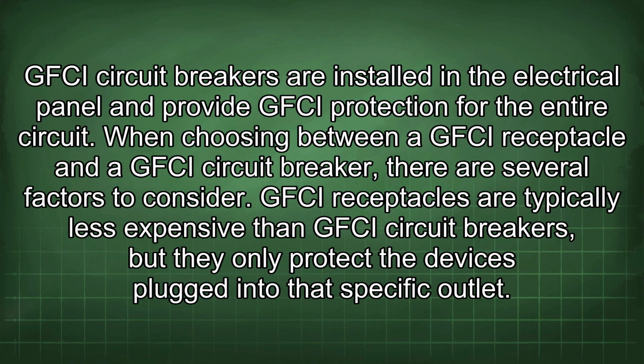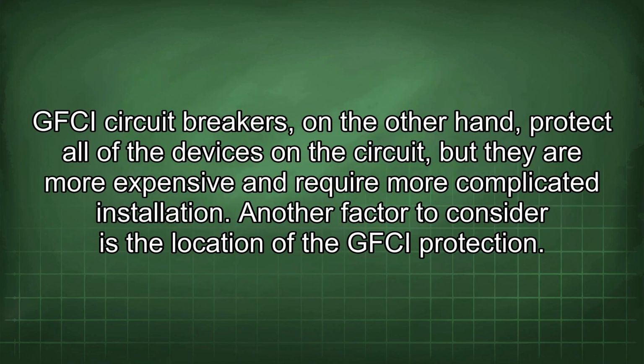When choosing between a GFCI receptacle and a GFCI circuit breaker, there are several factors to consider. GFCI receptacles are typically less expensive than GFCI circuit breakers, but they only protect the devices plugged into that specific outlet. GFCI circuit breakers, on the other hand, protect all of the devices on the circuit, but they are more expensive and require more complicated installation.